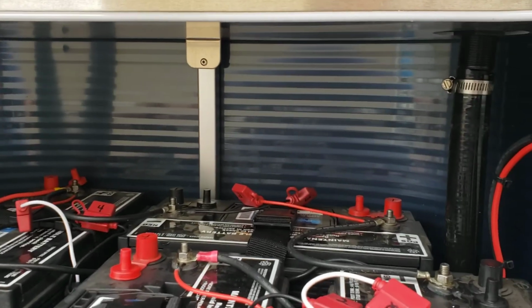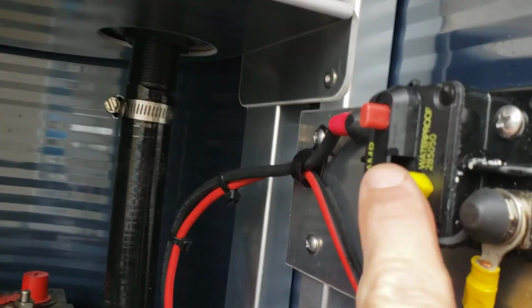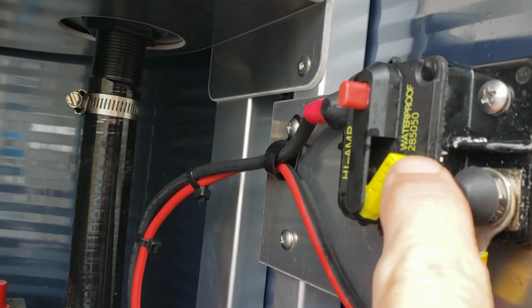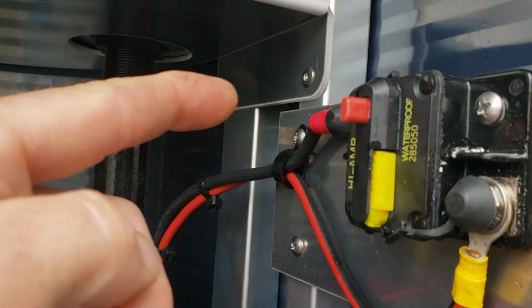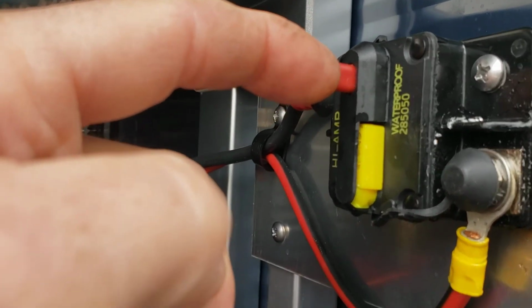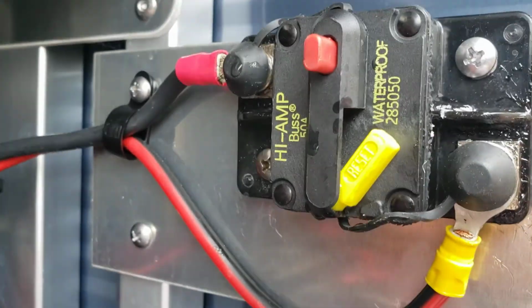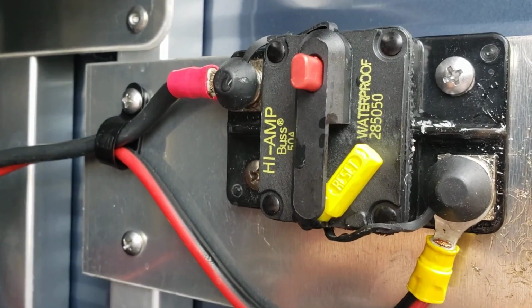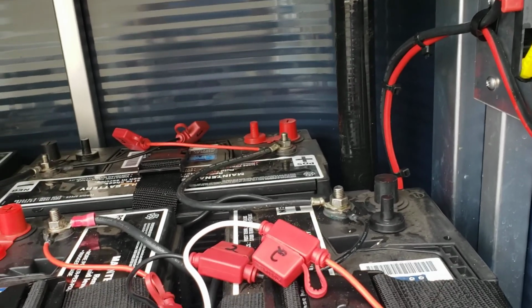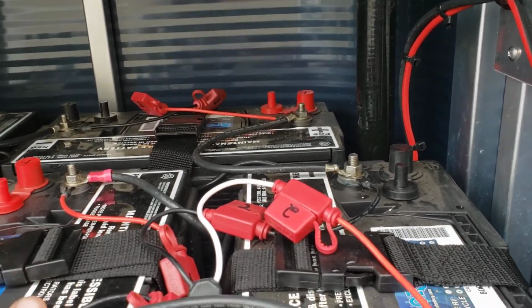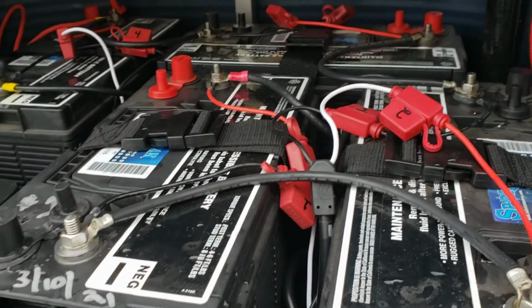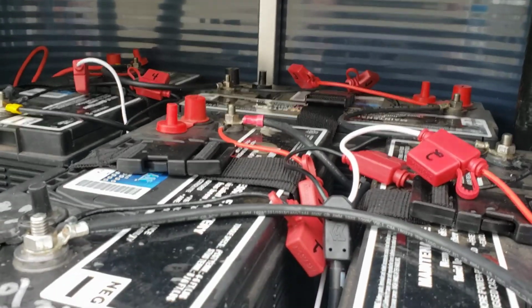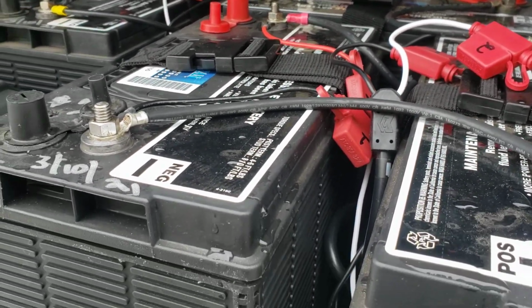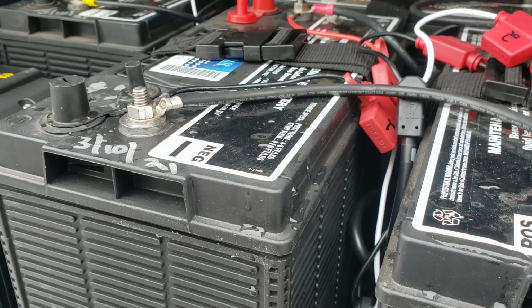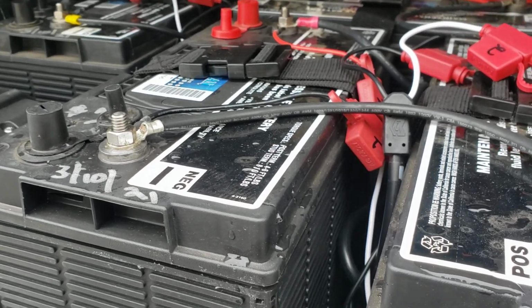In order to charge the batteries, you need to shut off the circuit breaker, which is done by pushing in this red button, and that releases that yellow arm. That is done so that the voltage from the batteries cannot be put through to the motor while the charger is plugged in, which means when the charger is plugged in, the voltage is a lot higher than it should be under normal operating conditions.